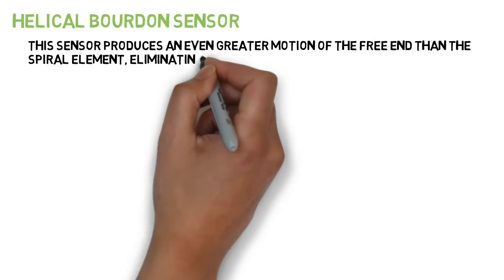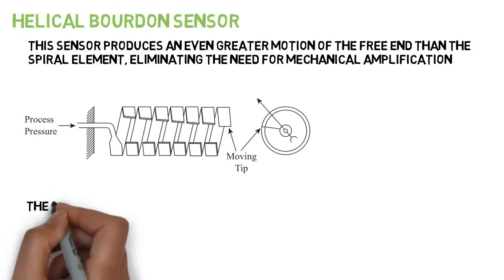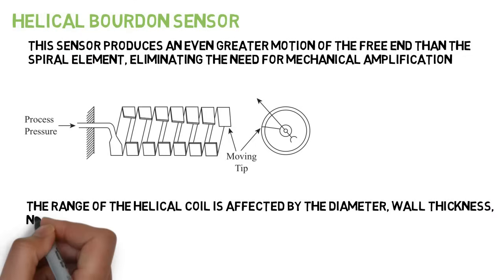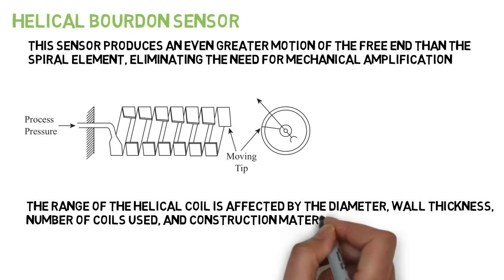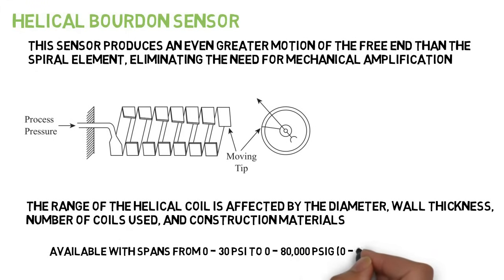Helical Bourdon pressure sensor. This sensor produces an even greater motion of the free end than the spiral element, eliminating the need for mechanical amplification. The range of the helical coil is affected by the diameter, wall thickness, number of coils used, and construction materials. High pressure elements might have as many as 20 coils, while low span sensors can have only two or three coils. Helical elements are available with spans from 0 to 30 psi to 0 to 80,000 psi.